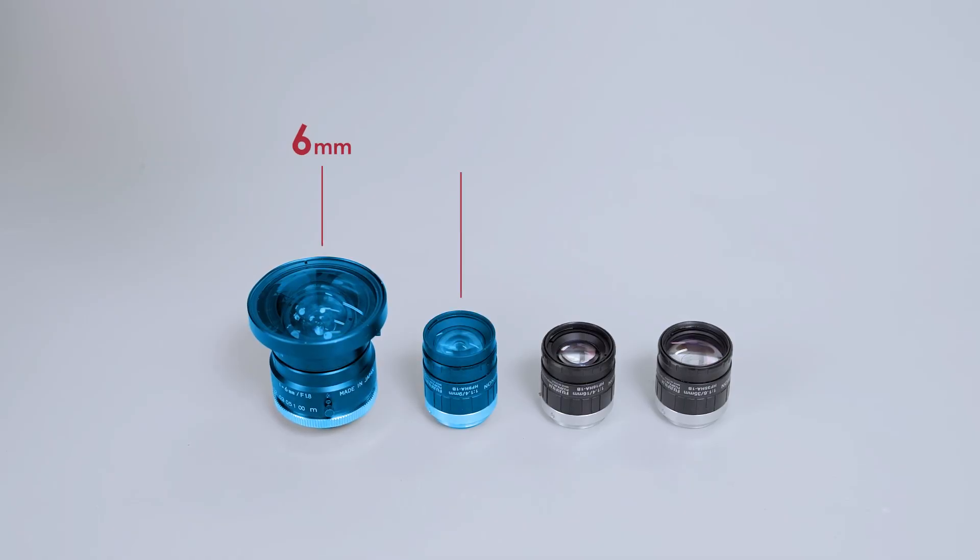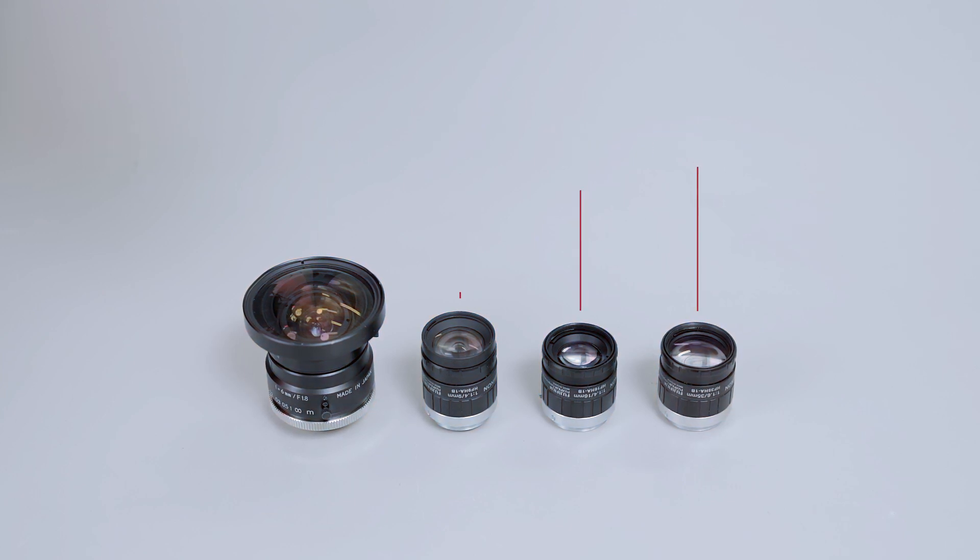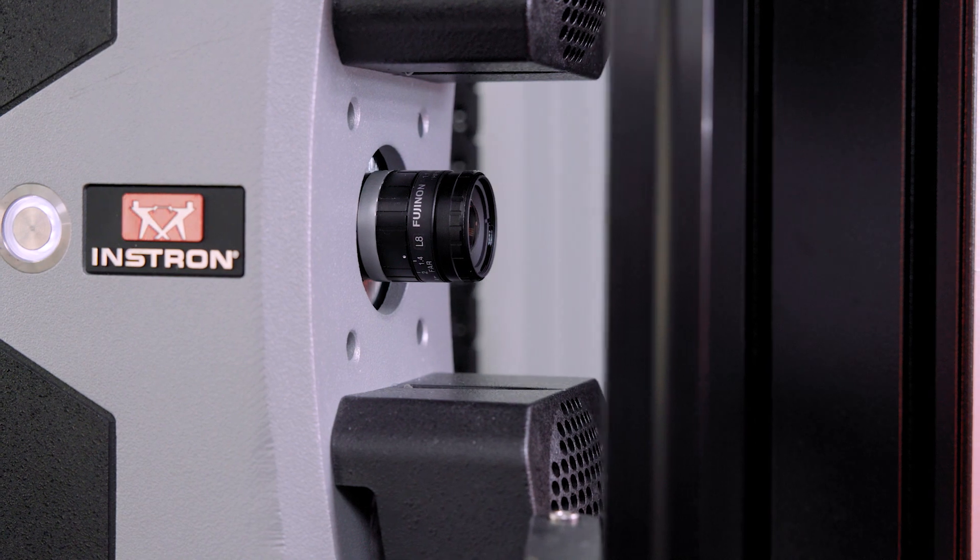Four field-of-view lenses are available to account for variety in accuracy, travel, and gauge length requirements, removing the need for additional extensometers.